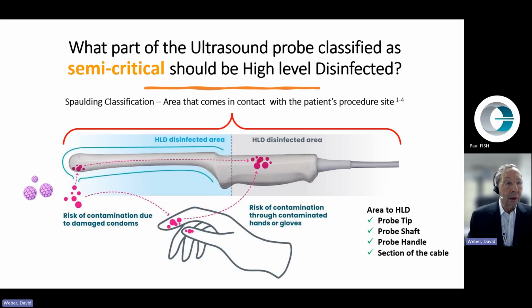Well, let's turn now and look at the probe itself. What part of the ultrasound probe is classified as semi-critical should be high-level disinfected? Again, under the Spaulding classification, the area that comes in contact with the patient's procedure site, as you can see on the left, should be high-level disinfected. And the risk of contamination due to damaged condoms is always present. So even if the probe has a condom, because condoms may be intrinsically with holes or may fail, we would still do high-level disinfection.